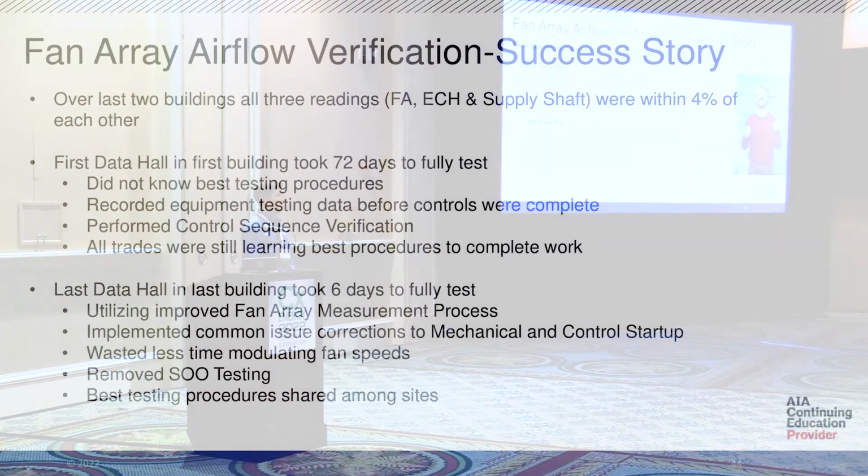A cool thing about working with this client is they love bringing everyone together in the same room and saying, all right, tell us your ideas. They love listening to whatever people have to say. They want you to work together, and that's what worked for us here. We were working with some NEBB firms, and one of the things I remember, we were talking about verifying our airflow monitoring station. We pulled out a pitot tube. One company pulled out a Velgrid. Another company pulled out an airfoil. Everybody kind of gets up there and says, hey, this is how I think we should verify this test rig.